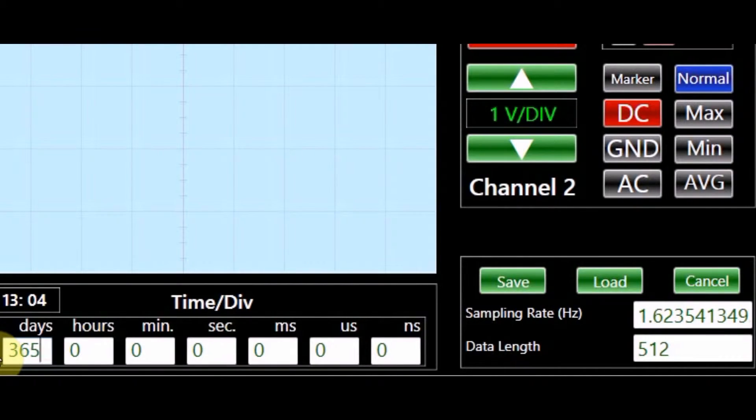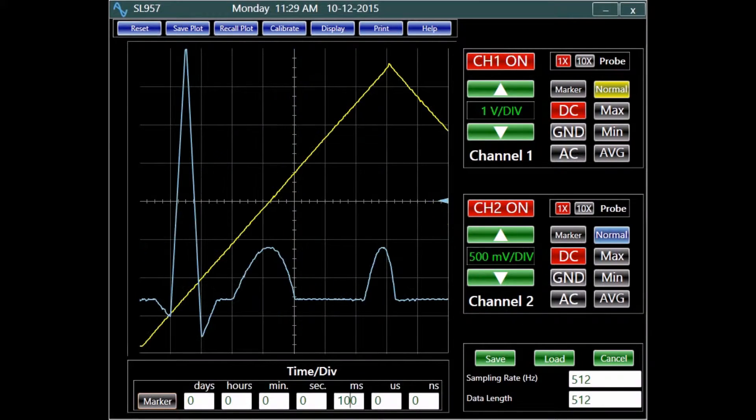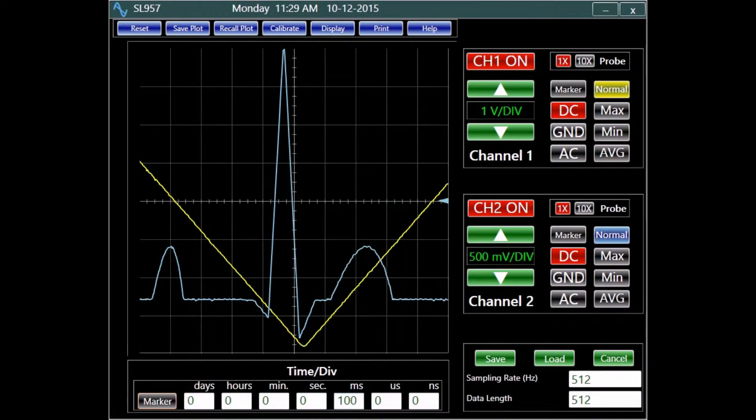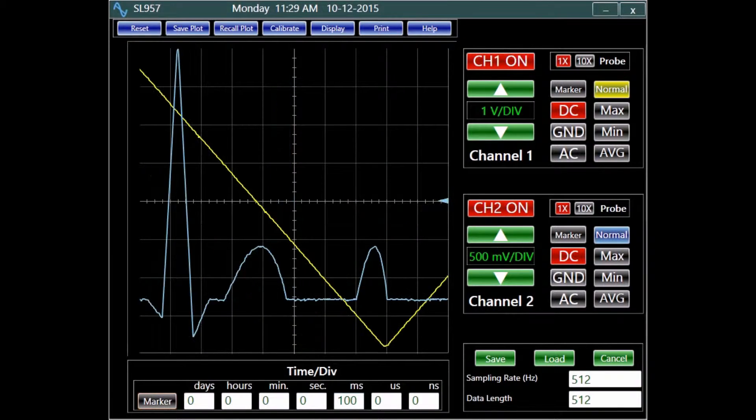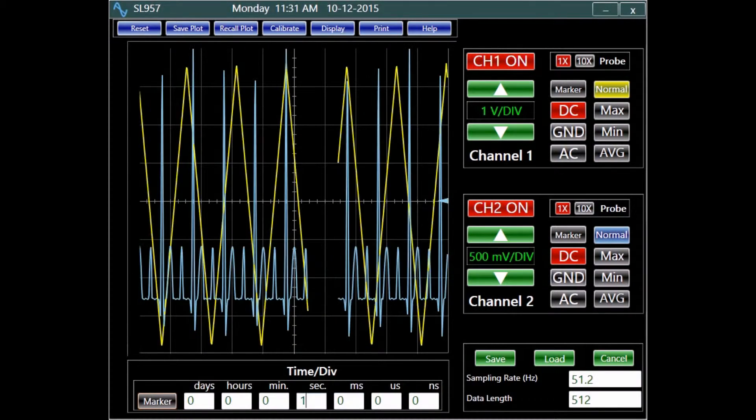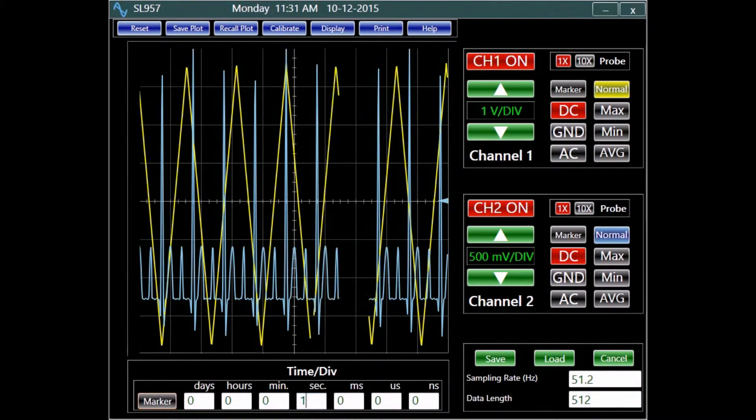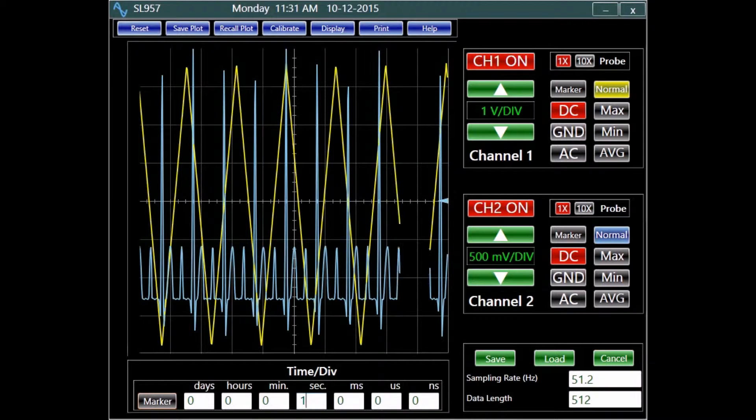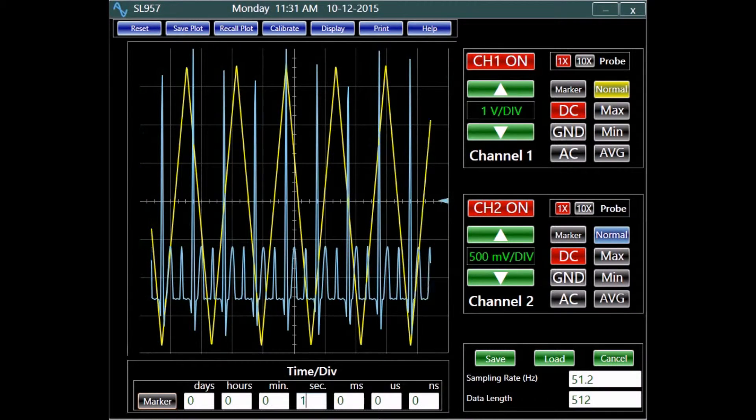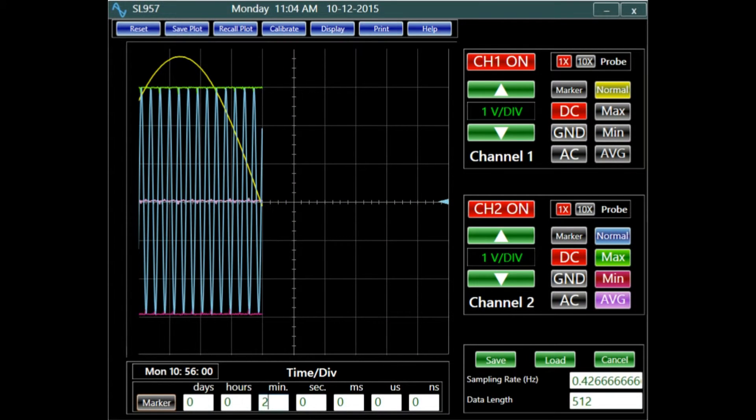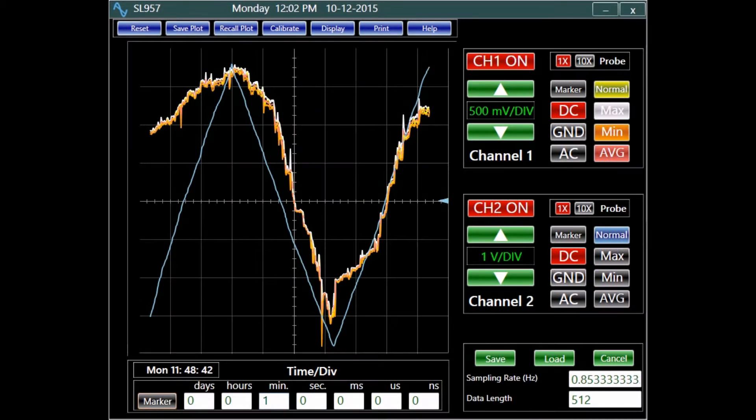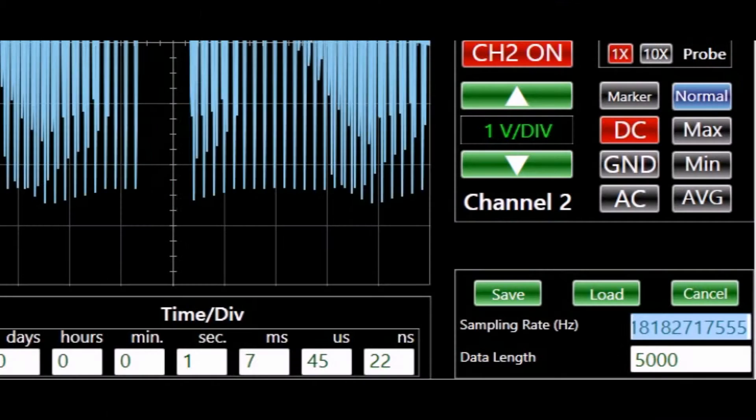For time resolution of 130 milliseconds per division or less, 100 million points of data can be recorded. For faster time resolutions, 1 megabyte of data can be recorded.